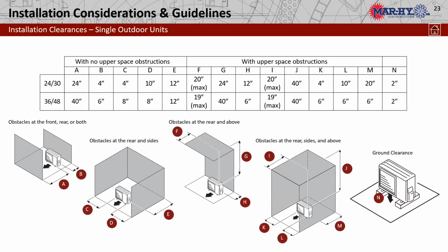Installation clearances. Depending on whether you're in a box or you've got limited obstructions, this usually isn't our application. Normally we're going to back up to the side of the house or the back of the house with very limited obstructions. In that particular case, on the 2 and 2.5 ton, we can be as close as 4 inches to the back of the coil from the house. And on the 3 and 4 tons, we can be 6 inches.